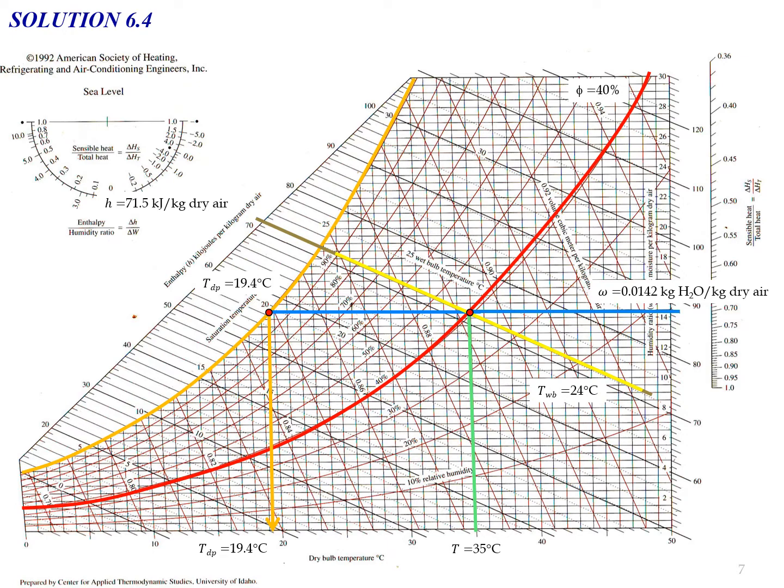And we can draw another line there to read the specific volume, which is 0.893 meter cube per kg of dry air. So as you can see from these two pieces of information, which are the dry bulb temperature and also relative humidity, we can find the rest of the information just by using this psychometric chart.